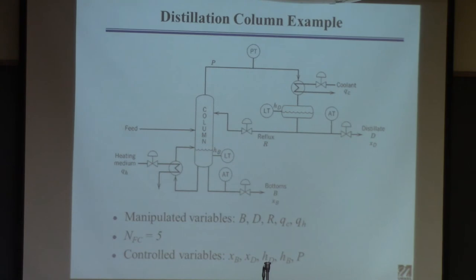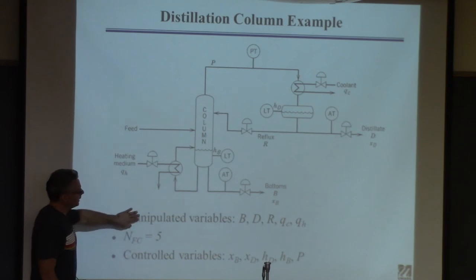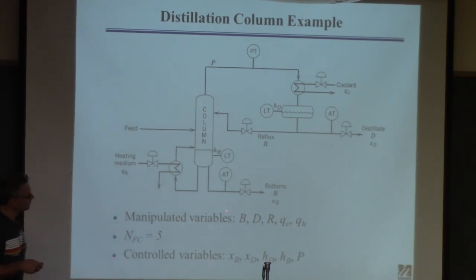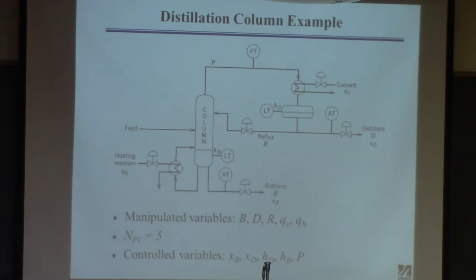One of the major control problems is maintaining inventories all over the plant. A typical plant has more than one column, maybe more than one reactor, exchangers, flash drums — lots of inventories. Looking at what we can manipulate: bottoms flow, distillate flow, reflux flow, coolant flow or duty, and heating duty. It turns out there are five degrees of freedom here, which is why we have five manipulated inputs. If there were eight degrees of freedom, we could choose eight.